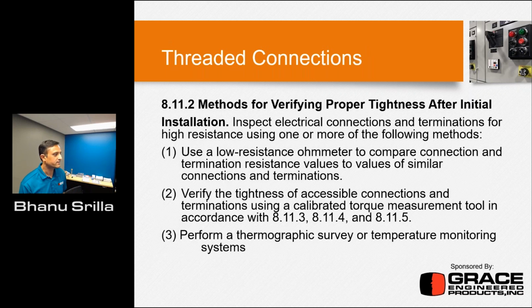Threaded connections. Methods for verifying proper tightness after initial: use the low resistance ohm meter to compare the connection terminals. And again, it's taken from 70B. Verify the tightness of accessible connection terminations and calibrate the torque measurement tool. So not only do you verify the torques on these connections, you also need to make sure that the torque tools are calibrated as well. And perform a thermography survey or temperature monitoring systems on a regular basis, right?